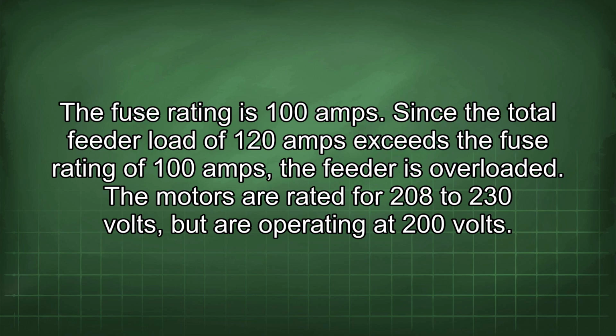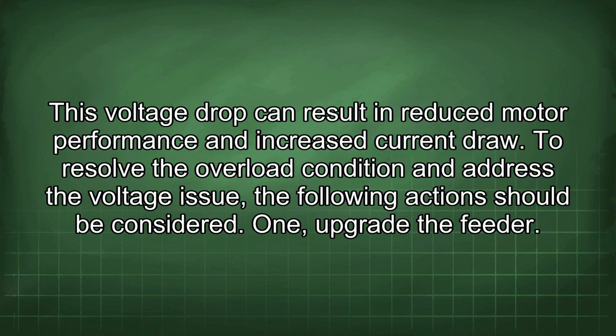The motors are rated for 208 to 230 volts, but are operating at 200 volts. This voltage drop can result in reduced motor performance and increased current draw. To resolve the overload condition and address the voltage issue, the following actions should be considered.